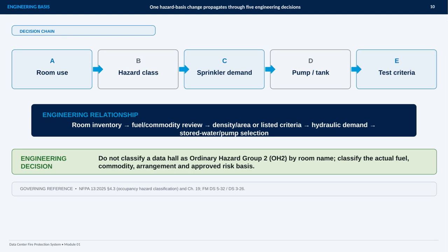The central idea is that a change in the hazard basis does not stay isolated. It propagates through a connected decision chain, from how the room is used, to how the hazard is classified, to the sprinkler demand, and ultimately to the pump, tank, and test criteria. The room name alone is not the classification. For a data hall, I need to review the actual fuel and commodity, the arrangement, and the approved risk basis. That means looking at the room inventory and the materials or equipment present, rather than assuming that every data hall belongs in ordinary hazard group 2.